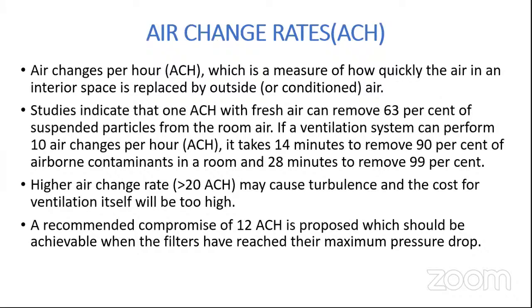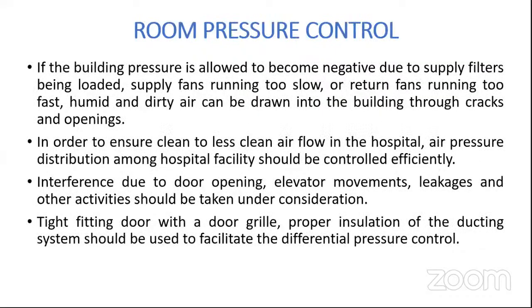Now, air changes in a hospital unit need to be good. What is air changes per hour? That's a measure of how quickly the air in an interior space can be replaced by the outside air. So if a ventilation system can perform 10 air changes, it takes 14 minutes to remove 90% of the airborne contaminants. When we are talking about healthcare facilities, it is suggested to have around 12 to 14 air change rates, whereas higher than 20 air change rates can cause turbulence, and the cost of the ventilation system would also increase.